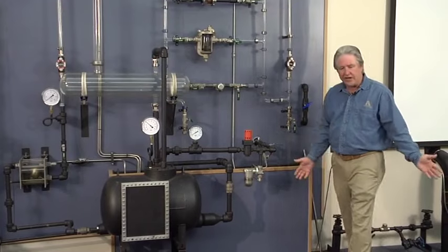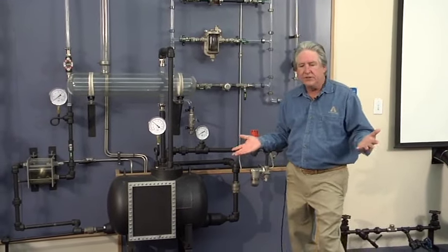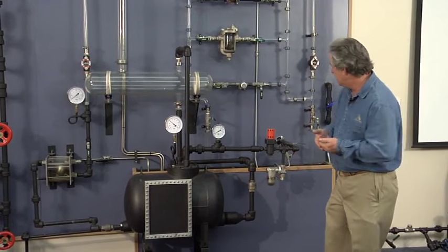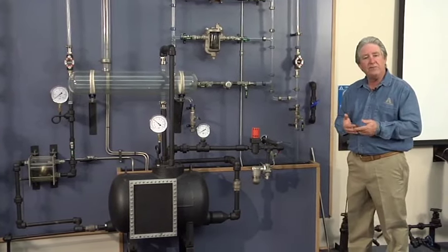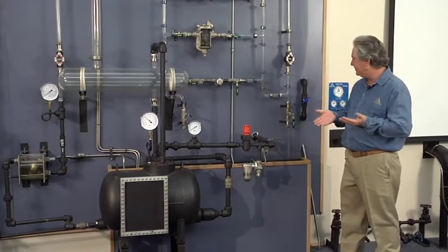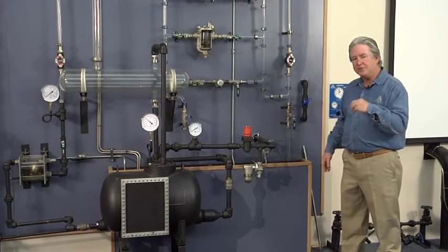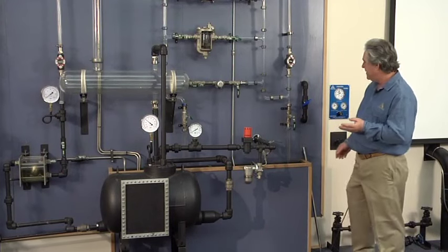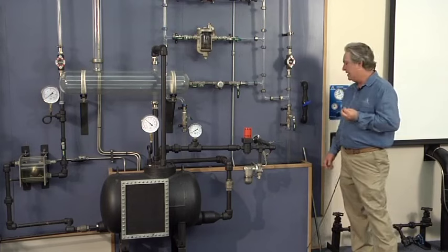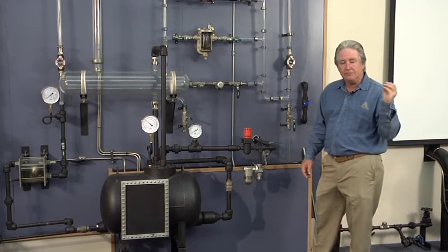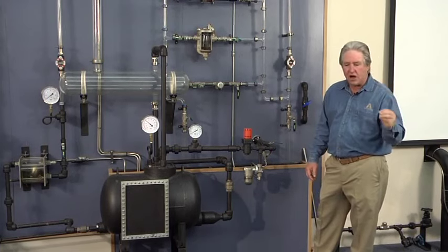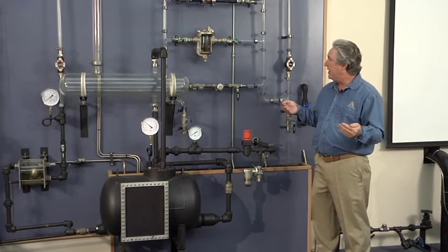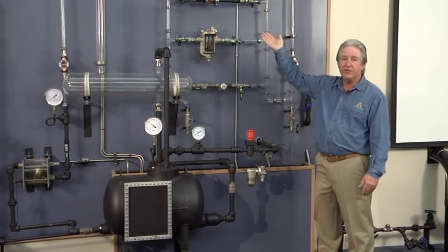As we continually try to help our customers optimize these systems, we know that hot condensate is worth a lot of money. So typically, we always try to recommend capturing this condensate. But when we start capturing condensate, that also creates other issues for us, okay? Like back pressure. In low pressure systems, back pressure is one of the most common problems that we incur when we try to evacuate condensate from a steam space.